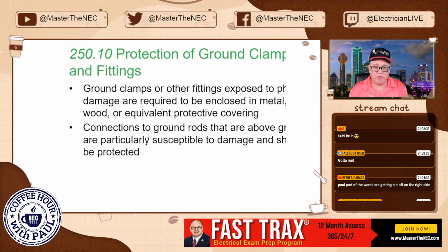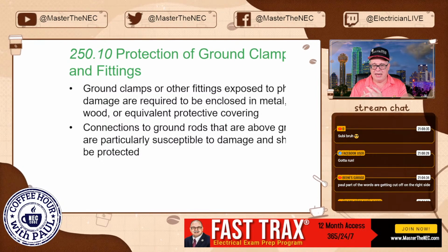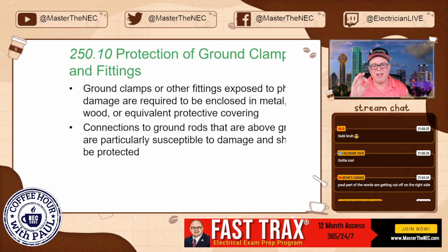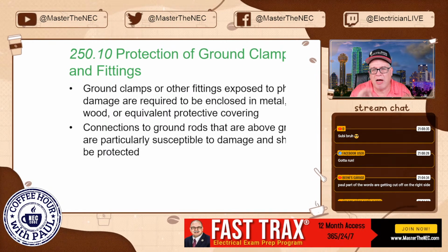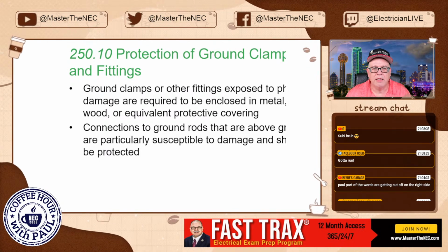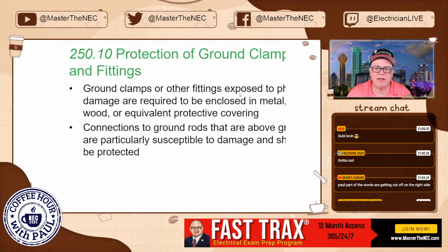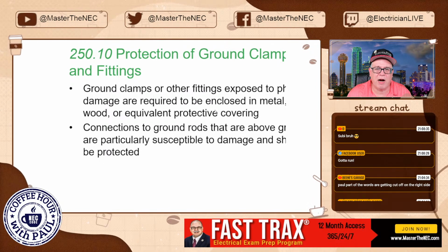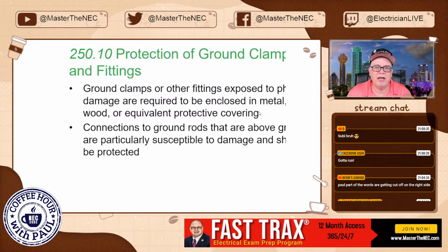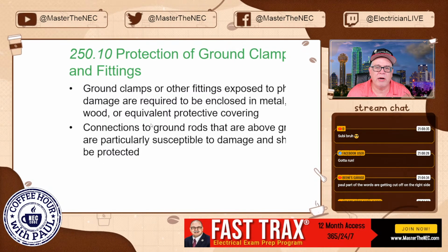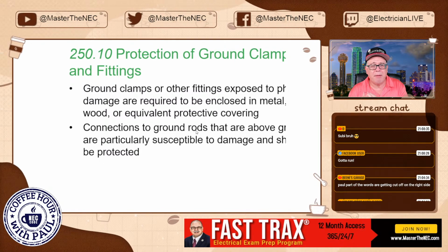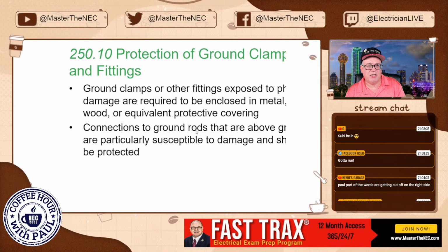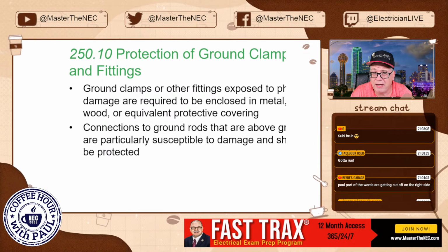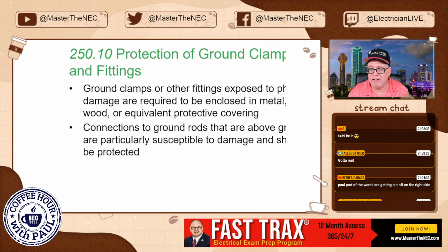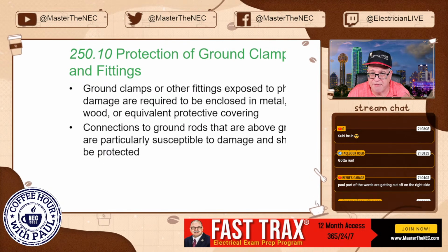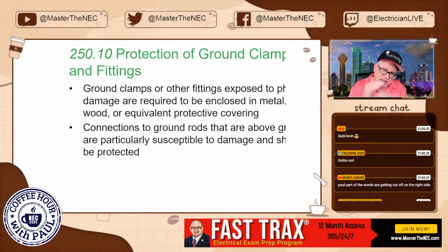So I'm going to put a ground clamp in. I'm going to put one of those acorn clamps on a ground rod. Okay. It says ground clamps and other fittings exposed to physical damage are required to be enclosed in metal, wood, or equivalent protective covering. How many times have you seen a ground rod outside not driven down into the earth like it's supposed to, right? 8 feet in contact with the earth, but it's just sticking up.